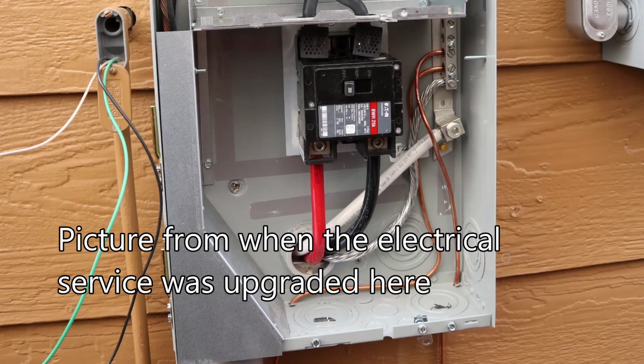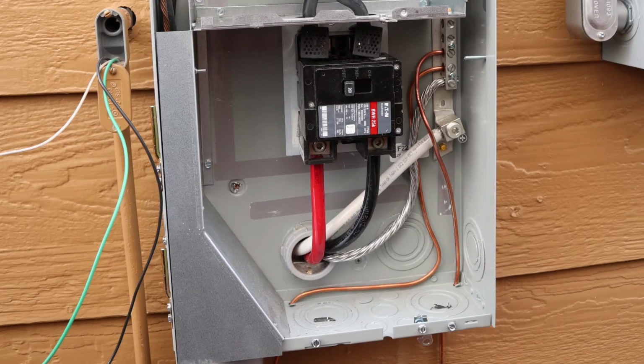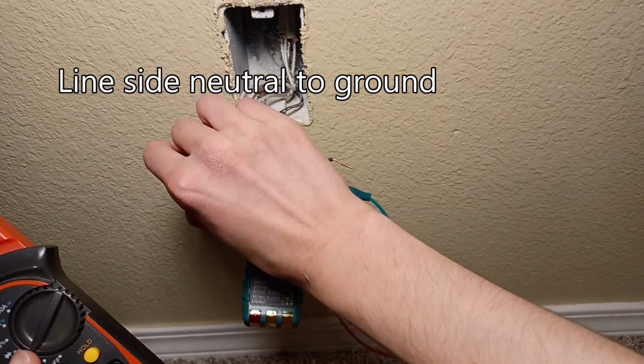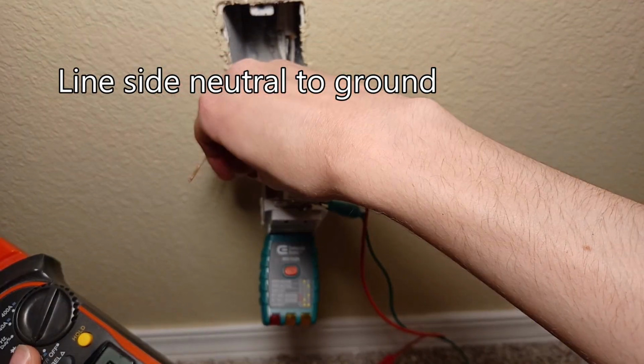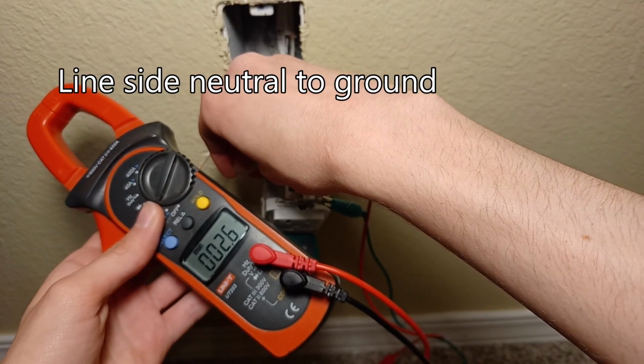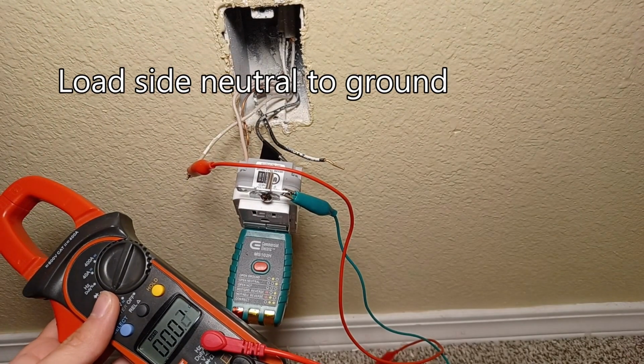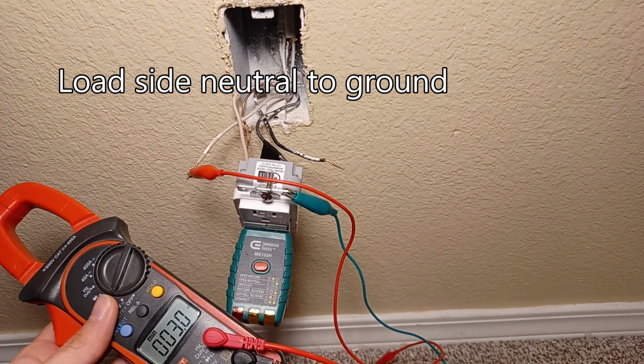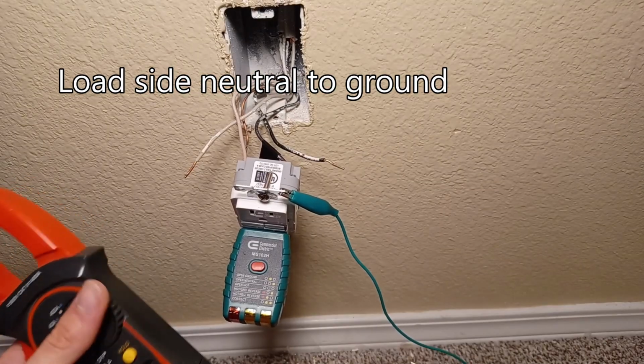The only place where the neutral and ground should be connected together is at the first point of disconnect, which is usually the main circuit breaker, which in this case is also in the meter box. So the neutral and ground are connected together right here in the meter box in our specific electrical installation. Because if I measure from the line to ground, it shows 2.5, 2.6 ohms. Measure from this one to ground, 2.9, 3 ohms?